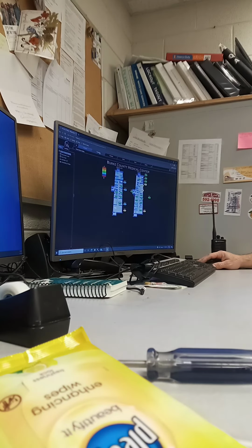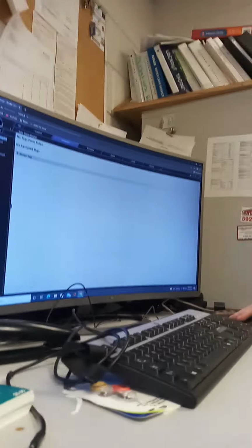So just kind of going across the top, graphics get you in there to change set points and look at how things are working. Properties, really just this control. If I click on a controller and I click on properties, it just gives me more data under this control program tab. Okay. If I click on Burke County Hospital up here, again, it's hierarchical. So what I want to see when I click on these top tabs is either everything or one individual piece of equipment. Right? So if I want to see everything, I click on the highest level in the tree.